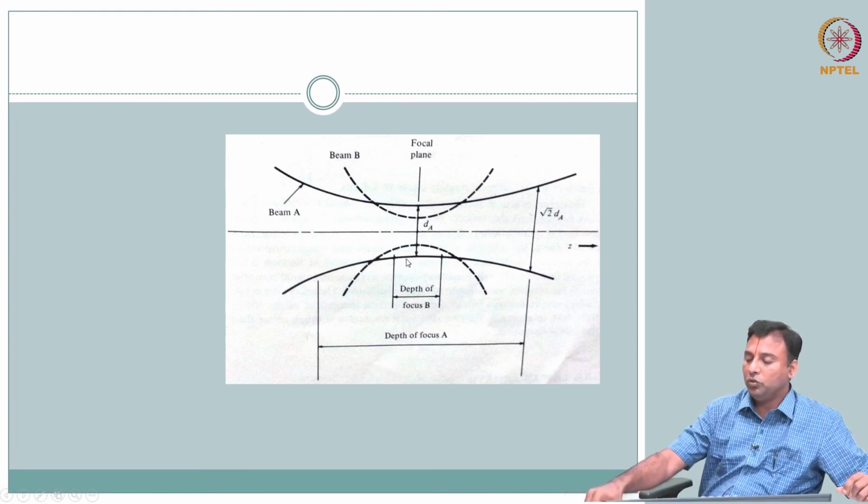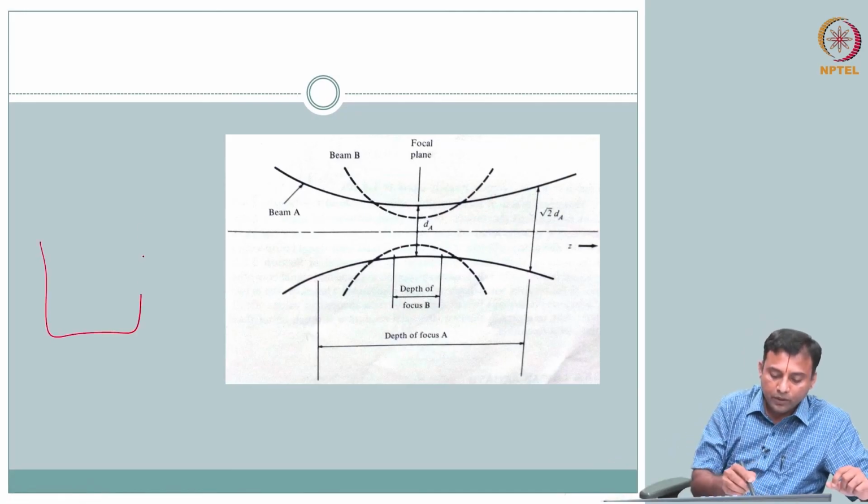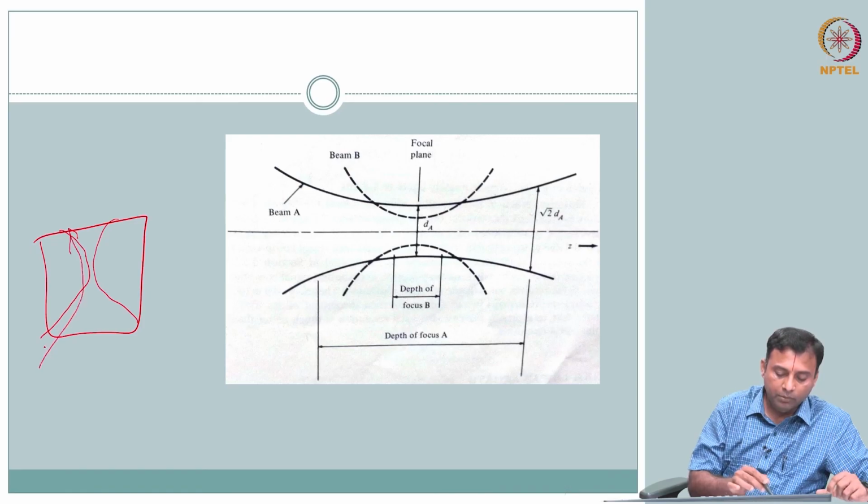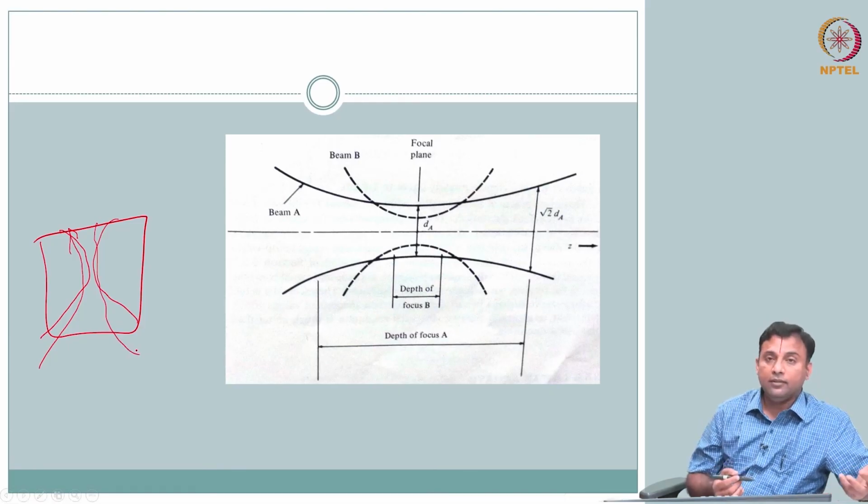If I want to do imaging, it is a trade-off whether I want this tight pattern, or whether I can live with a little wider one that will probably stay focused for longer. It depends on what you are imaging.